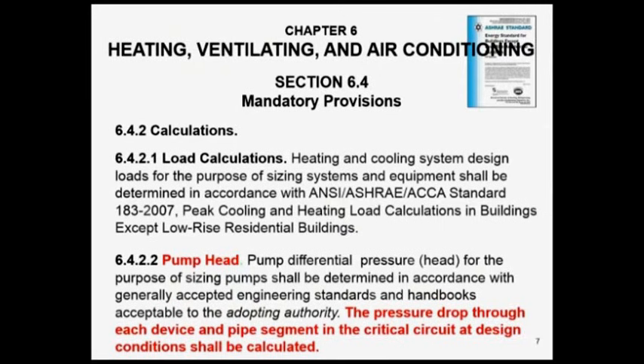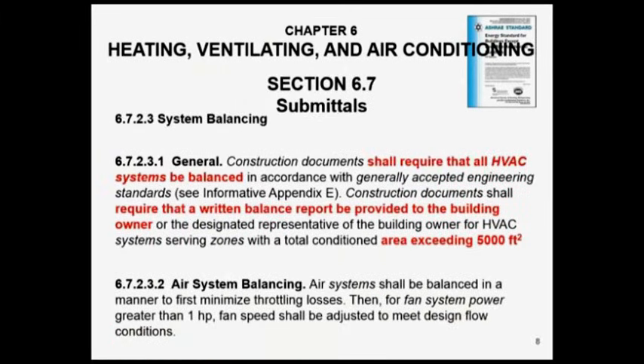So that means you need to know where that critical path is, and that also becomes extremely important when you start talking about balance. What does it say about balance in 90.1? Interesting. It says, and here's a statement in red, might be important for you to understand, that it's required. It's required on systems be balanced on any building over 5,000 square feet. And, you know, a 5,000 square foot building is fairly small.